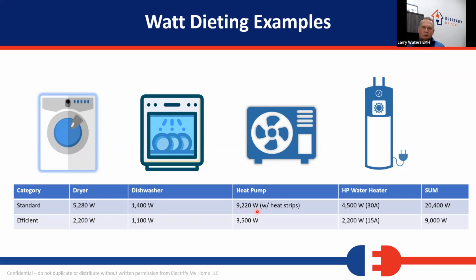If we put in a really good inverter heat pump system, we're running down around 3,500 watts. So once again, I can calculate this in as my load for the HVAC system as long as I downsize my breakers. Heat pump water heaters, we can do a 30 amp or a 15 amp or even now 110 volt plug-in, but that's going from 4,500 watts for a 30 amp to 2,200 watts for a 15 amp. So if we just did these measures in the average home, we're saving 11,400 watts off this system, all that we can use for something else or not use at all.